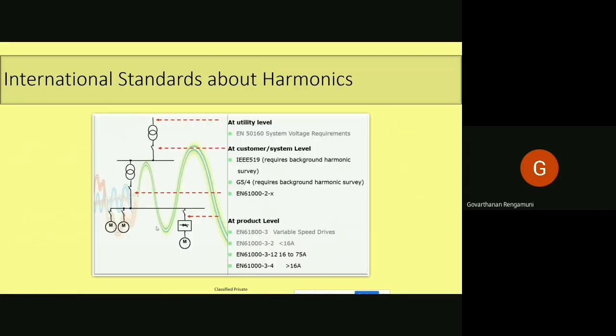So there can be a question: how to design a power converter without harmonic pollution, and what level of harmonics is acceptable? Some international standards help us design a system with the prescribed harmonic limits. So we need to account for these factors while we start designing a power converter, the grid connected power converters.